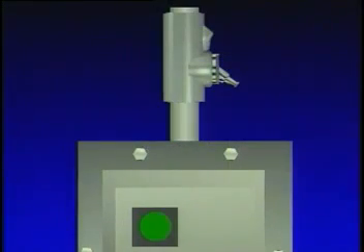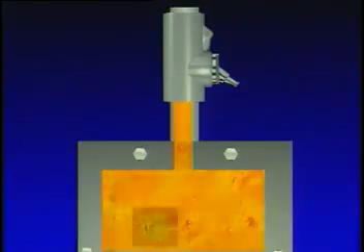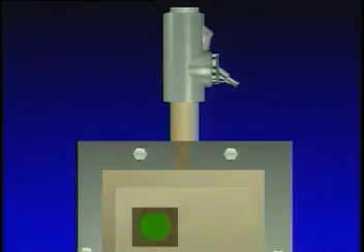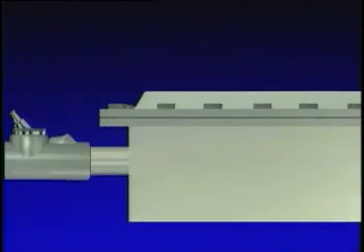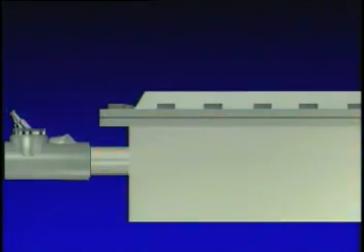A properly installed sealing fitting acts as a barrier to stop burning gases from traveling through the conduit to other parts of the system. Once the burning gases have been stopped by the sealing fitting, they escape through the enclosure's access joints, which are machined to close tolerances to create flame paths. These joints sufficiently cool the burning gases to a temperature which will not cause ignition of the outside atmosphere.